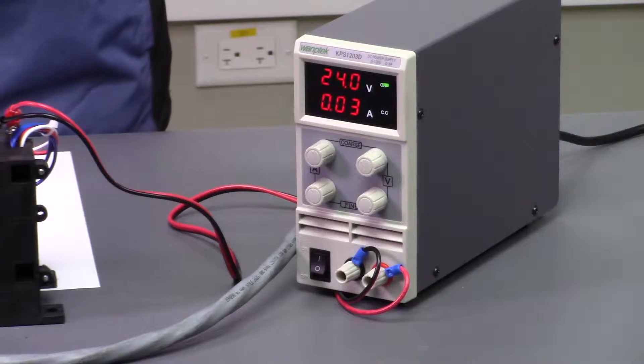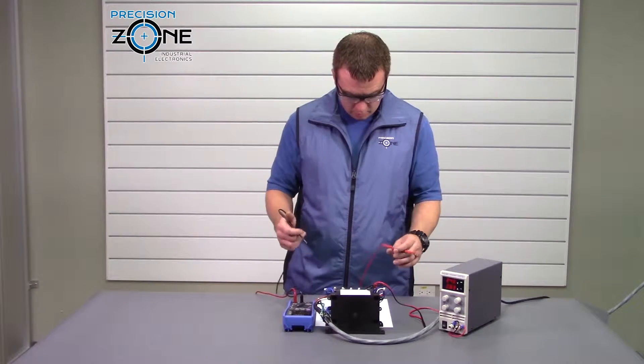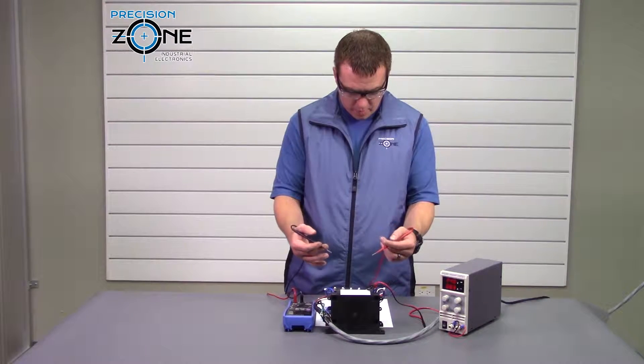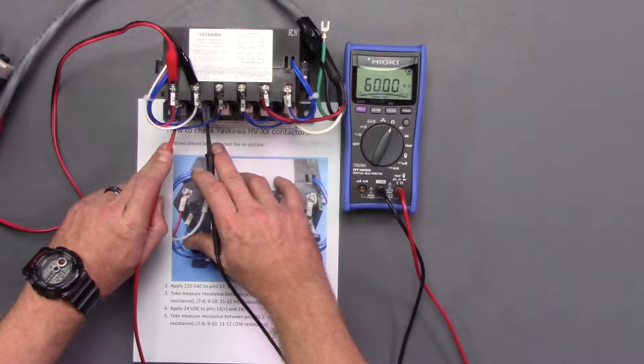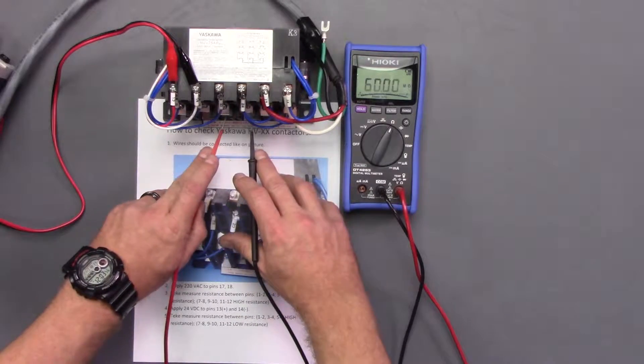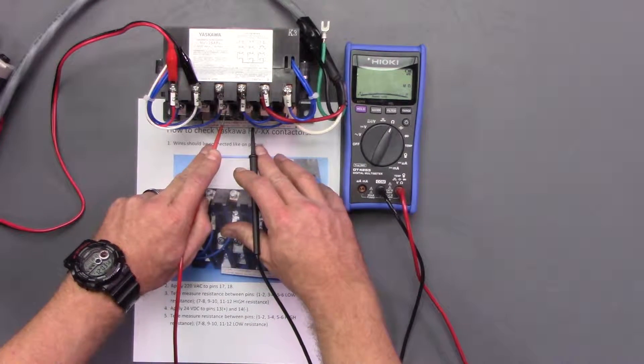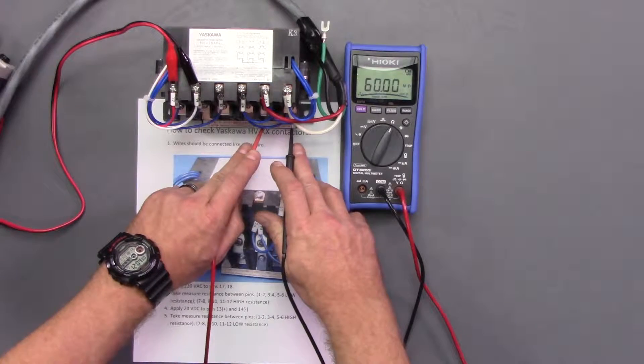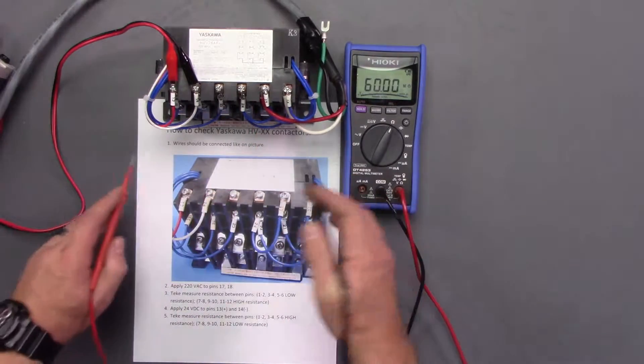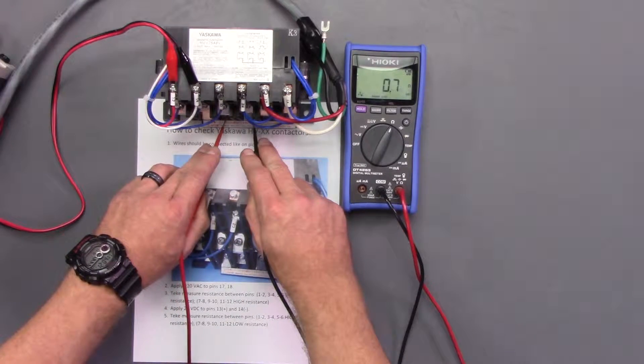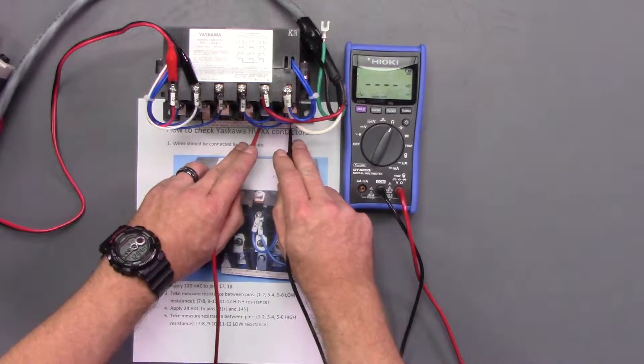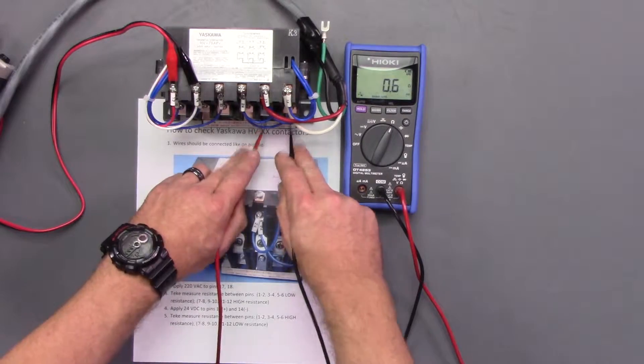Okay, now that the contactor's engaged, everything we checked on the first step will be the exact opposite on the second step. So we're going to go between 1 and 2, nothing, 3 and 4, nothing, 5 and 6, nothing. And then these should all be shorted. Which they are.